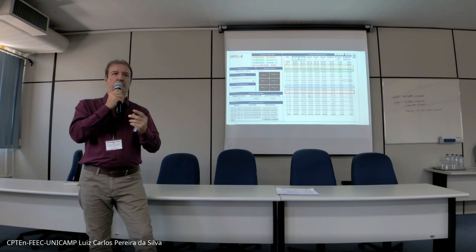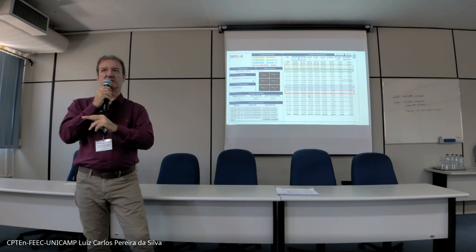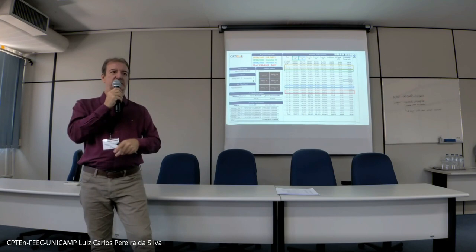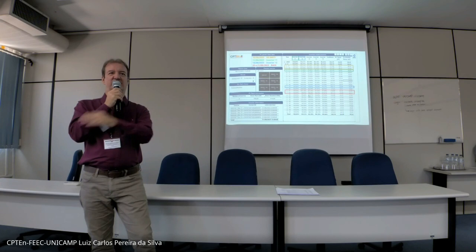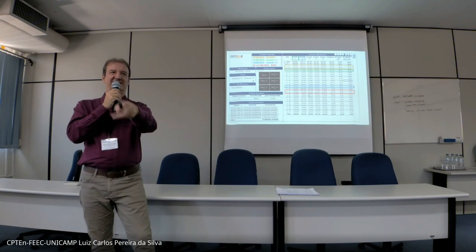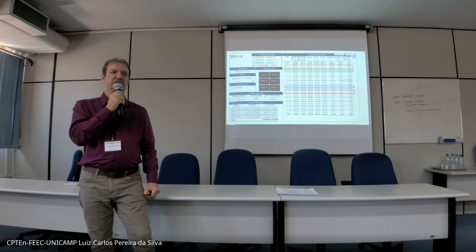But if you clean the panels, 22%. So my boss decided to create our own team, schedule the maintenance, and we are cleaning all 24 PV plants in a scheduled way. And we are monitoring the benefits of this cleaning. 20% is a large amount of generation that you are losing.